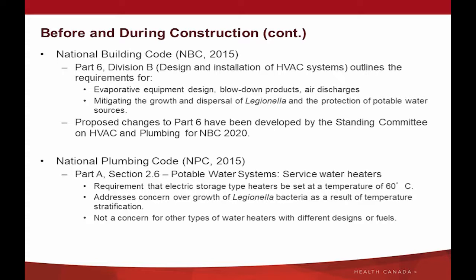Provisions under the Plumbing Code dealing with Legionella are in Part A, Section 2.6, Service Water Heaters, requiring that electric storage type water heaters be set to 60 degrees Celsius. This is to address the concern for Legionella growth at temperatures below 60 degrees due to temperature stratification that can occur in this type of water heater. For other water heater types and fuels, this has not been identified as a concern.